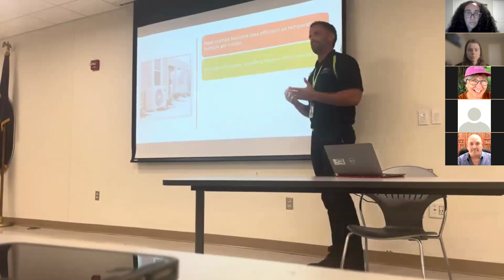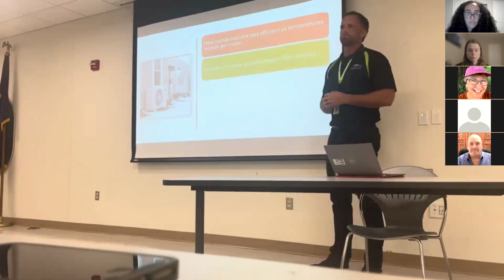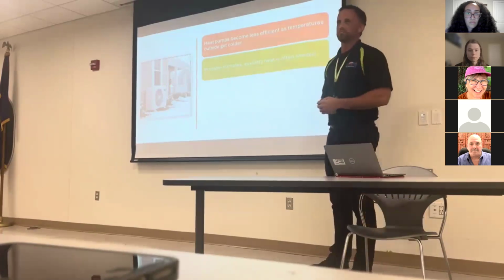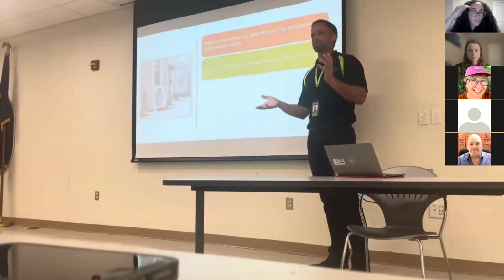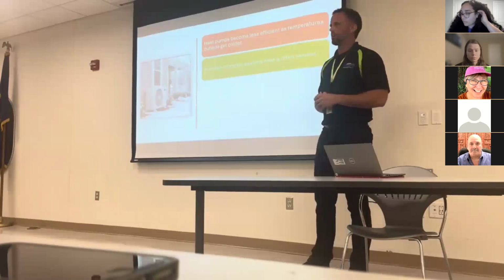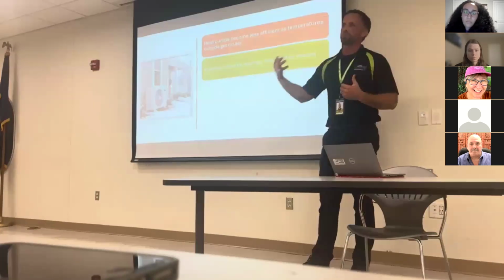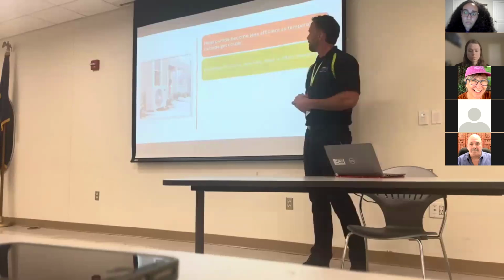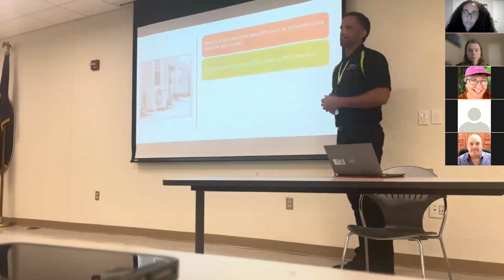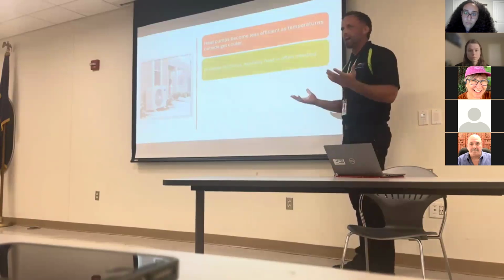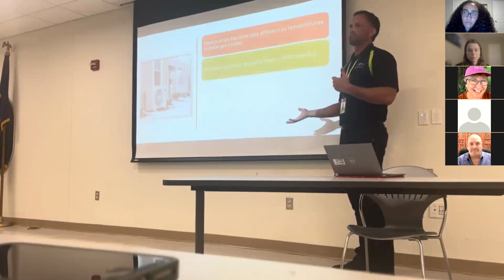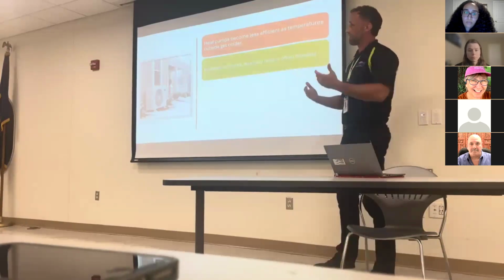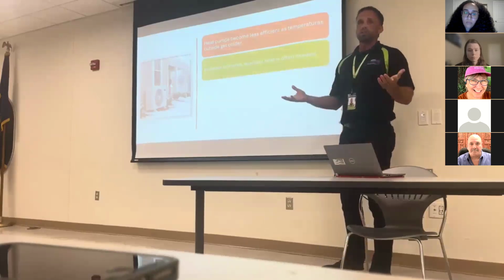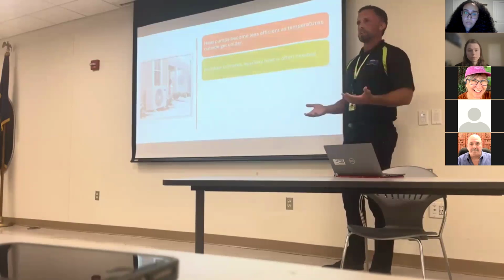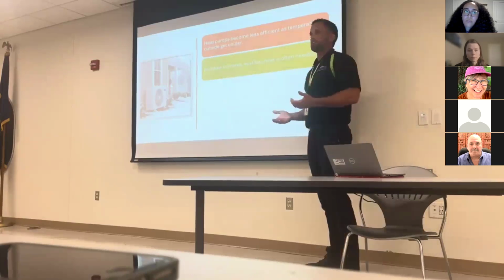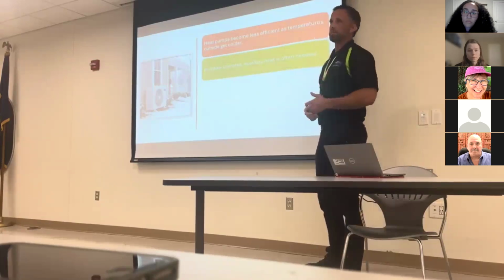Yeah, typically in Indiana, your heat pump will cover 70% of the heating season, and for 30% you're going to need some type of auxiliary heat. That depends on your comfort level and how we set the controls up. Some people just don't want to feel it get too cold at all, so they'll kick on the auxiliary heat sooner. Typically I'd say on average 70% of the time, it's mild out, it's 40 degrees out, you don't need any auxiliary heat. But when it gets down to 20 or below, that auxiliary heat's going to run more and more. But the goal is to keep the heat pump running as much as possible because it's so much less expensive to run a heat pump than any type of auxiliary heat.